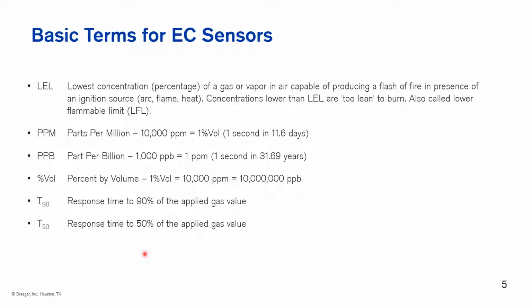Talking about percent by volume, generally when we talk about oxygen, we're referencing that in a percent by volume. Anywhere from 0 to 25% for a standard sensor, or even up to 100% by volume for one of our partial pressure type sensors. The response time of a sensor is also a very important component. Generally, response time is expressed as how much time does it take to get to a certain response. So we have a T90, that is how much time does it take to get to 90% of your gas value. We have a T50 that's to 50%. I've also seen T20 response times in specifications.